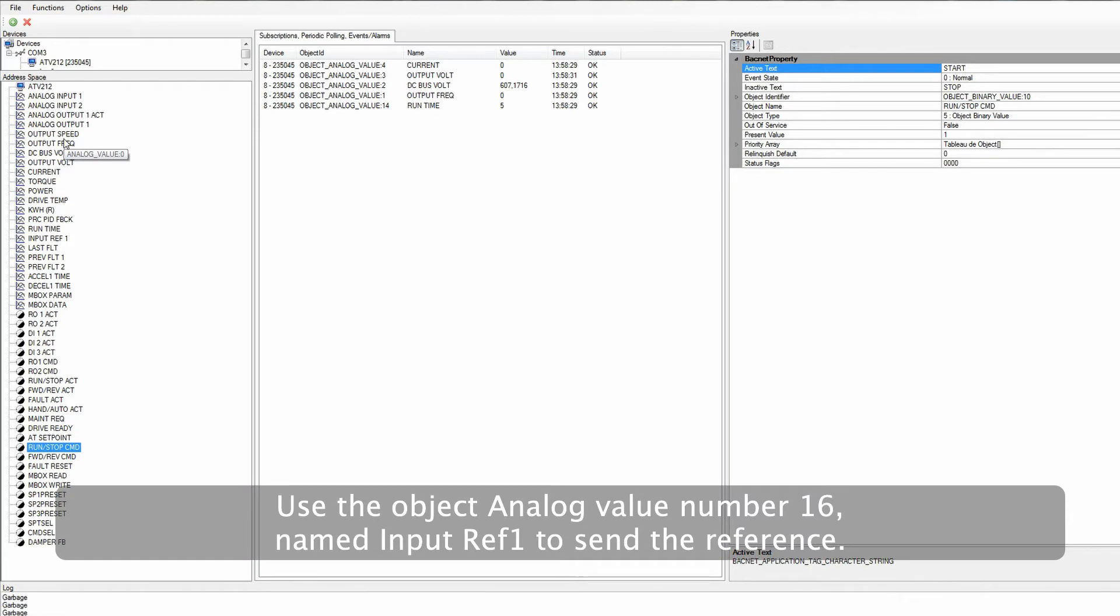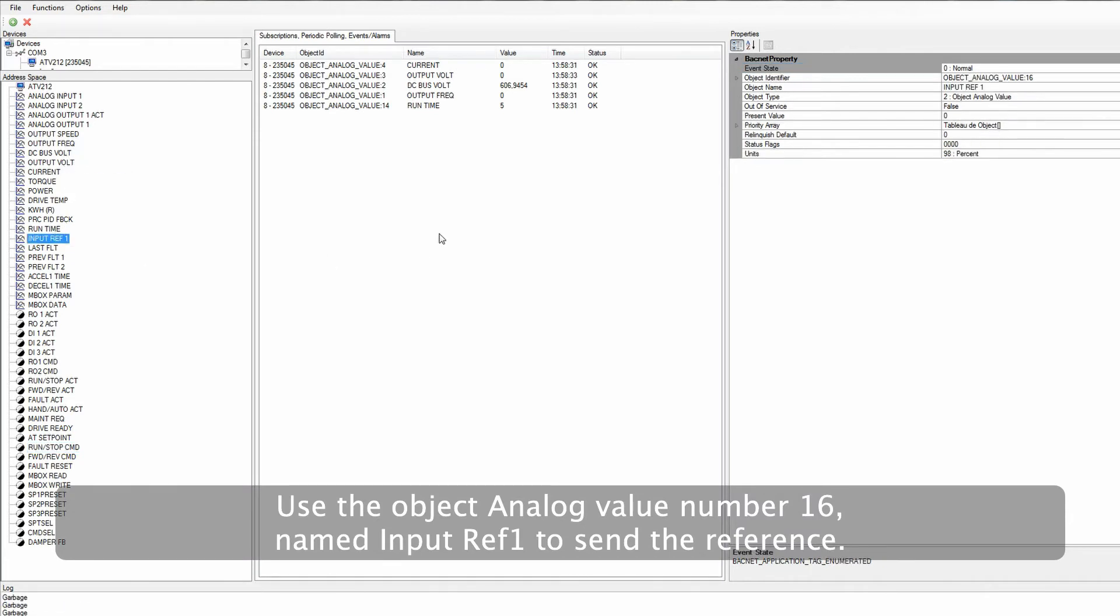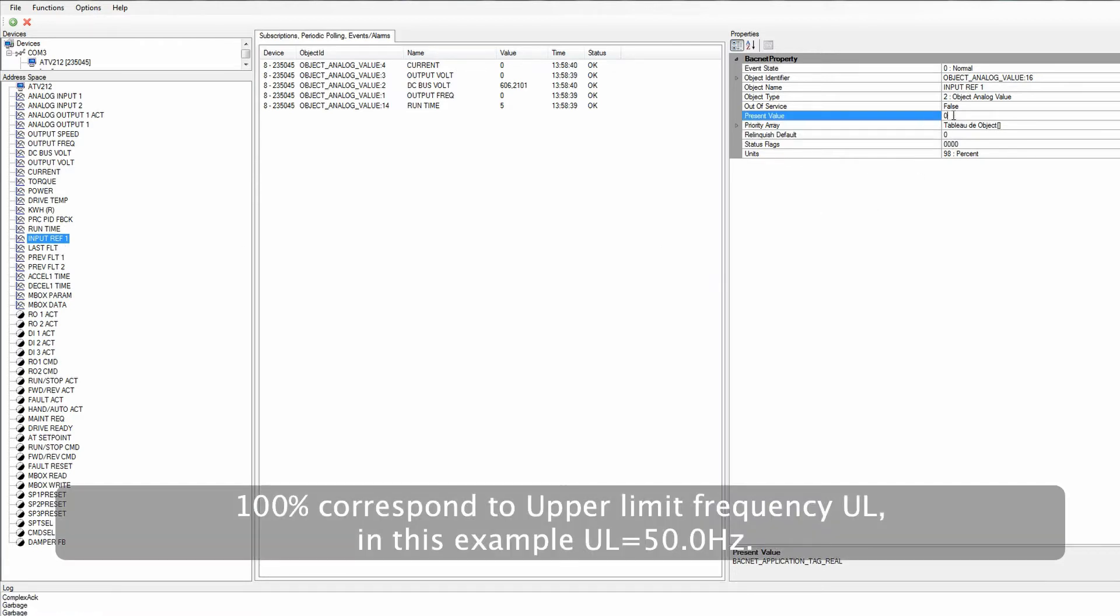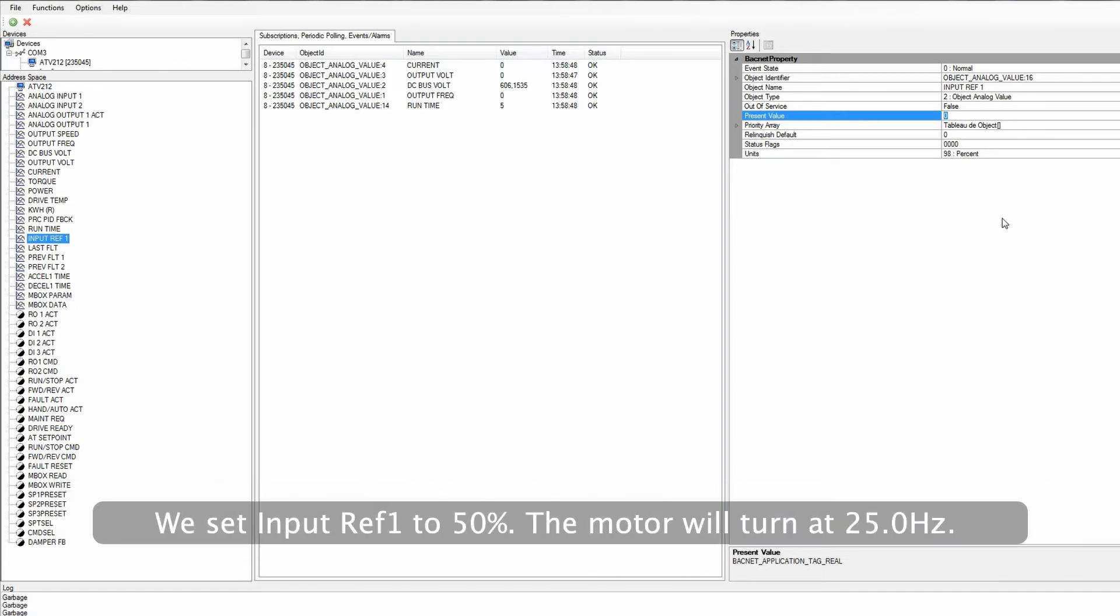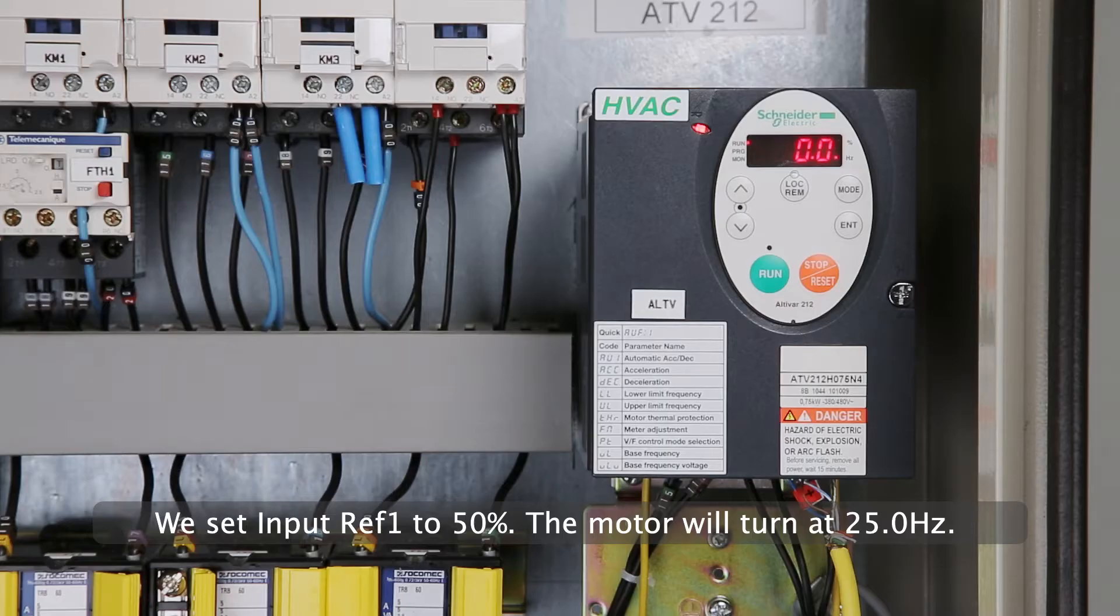Use the object analog value number 16, named Input Ref1, to send the reference. 100% correspond to upper limit frequency UL. In this example, UL equals 50.0 Hz. We set Input Ref1 to 50%. The motor will turn at 25.0 Hz.